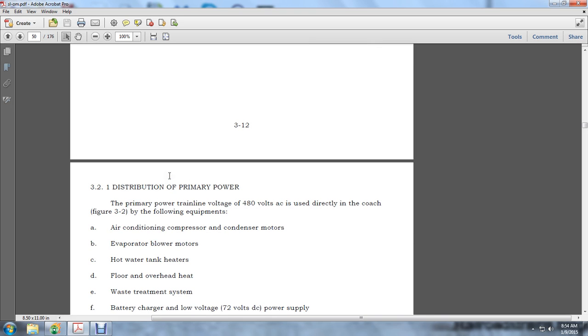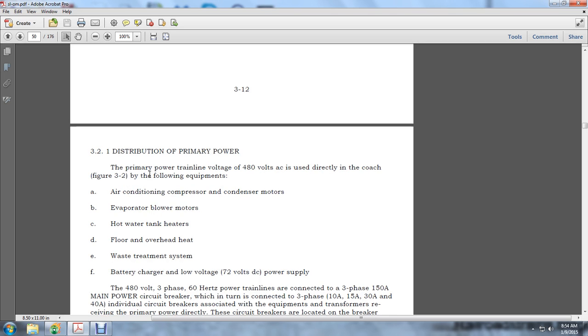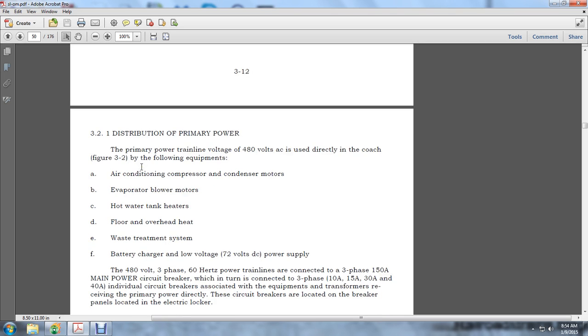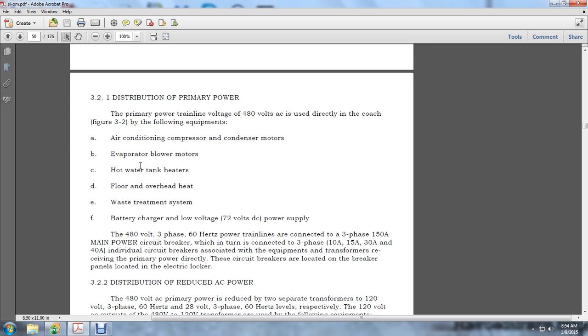3-2-1, distribution of primary power. The primary power of 480 volts is used directly in the coach for the following equipment: the air conditioner compressors, the condenser motors, the evaporator blower motors, the hot water tank heaters, the floor and overhead heat, the waste treatment system, and the battery charger and low voltage 72 volt DC power supply. The 480 volt 3-phase 60 Hz power train line is connected by the 3 phases of the 150A main power circuit breaker, which in turn is connected by the 3-phase 10A, 15A, 30A and 40A individual circuit breakers associated with the equipment and transformers receiving the primary directly. The circuit breakers are located in the breaker panel located in the electrical locker.